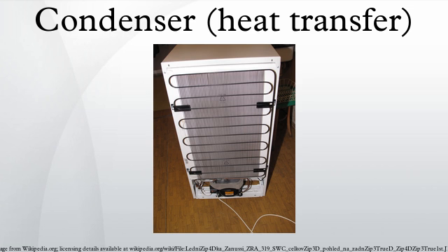Examples of condensers: a surface condenser is an example of such a heat exchange system. It is a shell and tube heat exchanger installed at the outlet of every steam turbine in thermal power stations. Commonly, the cooling water flows through the tube side and the steam enters the shell side where the condensation occurs on the outside of the heat transfer tubes.